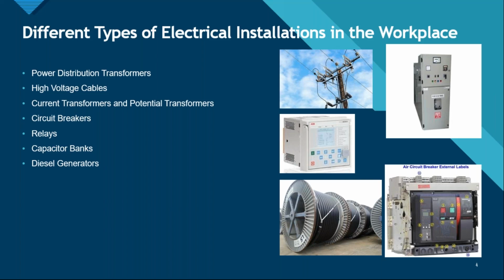Then there can be capacitor banks. Basically, capacitor banks, you can think of them as batteries, right? In case of emergency processes, they basically store the electricity and also help in increasing the power factor, right? The power factor can range from 0 to 1. If the power factor is closer to 1, basically that's less electricity bill, right? So a lot of industries use capacitor bank panels, right? So if there are capacitor bank panels, sometimes if there is testing and maintenance going on an electrical panel, if the capacitor banks are not disconnected, there can be additional supply coming from the capacitor bank that you might not be aware of, and that might also lead to an arc flash or an arc blast.